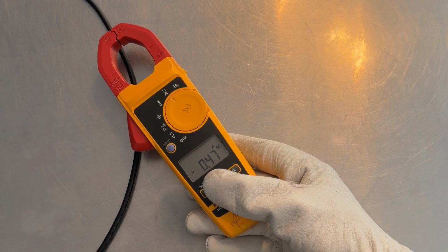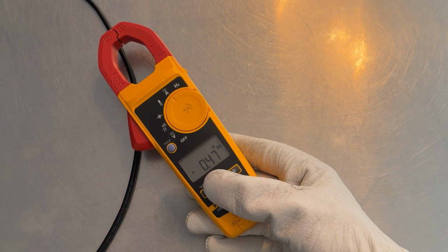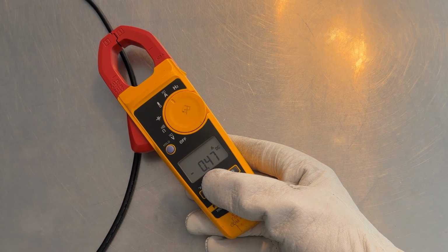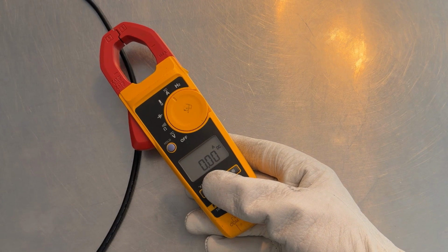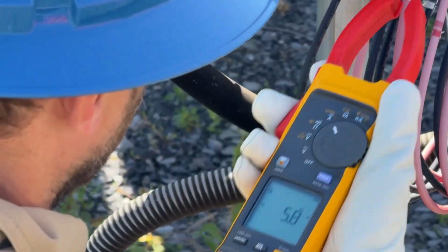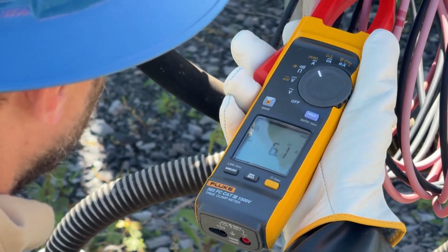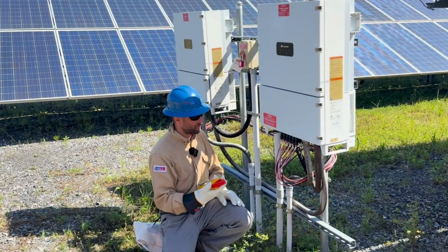wire. We want to zero it out when it's in the position that we're going to use it in and when it's near the wire that we're going to be measuring. We're zeroed out. Let's head back to the field. All right, so we've got 5.8 amps there. 6 amps. Strings are relatively consistent.